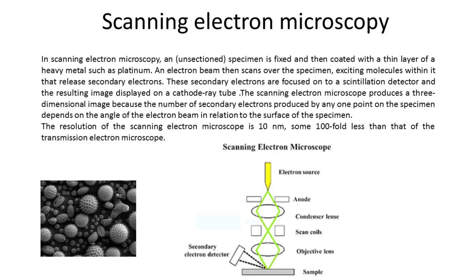Scanning Electron Microscopy: In Scanning Electron Microscopy, an unsectioned specimen is fixed and then coated with a thin layer of a heavy metal such as platinum. An electron beam then scans over the specimen, exciting molecules within it that release secondary electrons. These secondary electrons are focused onto a scintillation detector and the resulting image displayed on a cathode ray tube. The scanning electron microscope produces a three-dimensional image because the number of secondary electrons produced by any one point on the specimen depends on the angle of the electron beam in relation to the surface of the specimen.